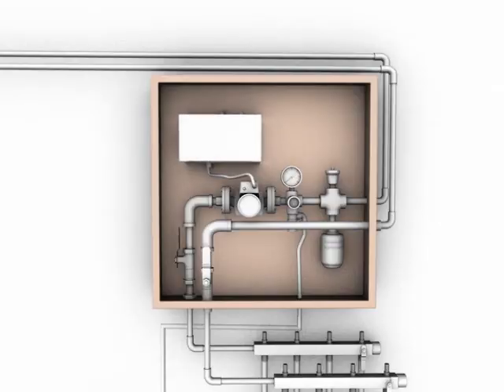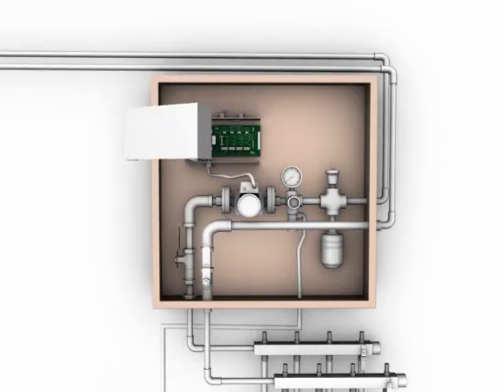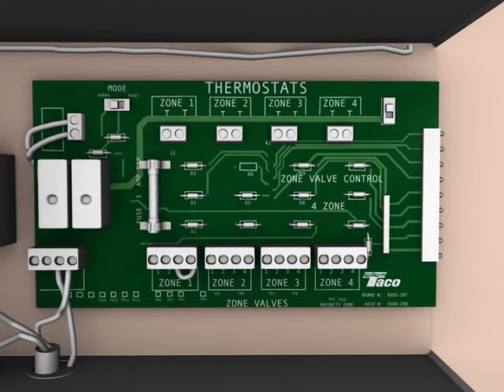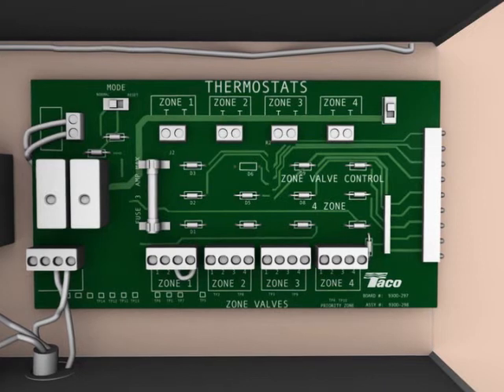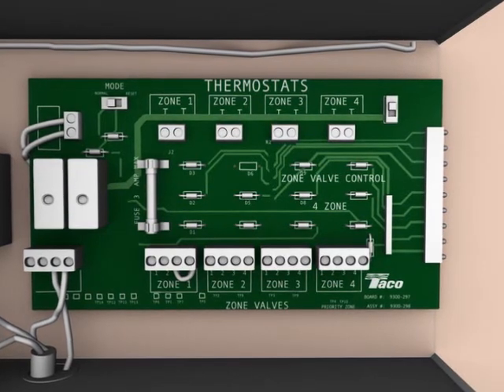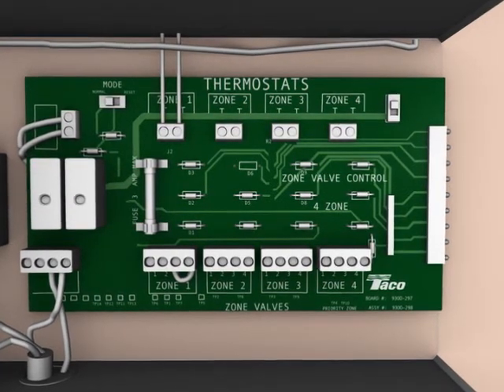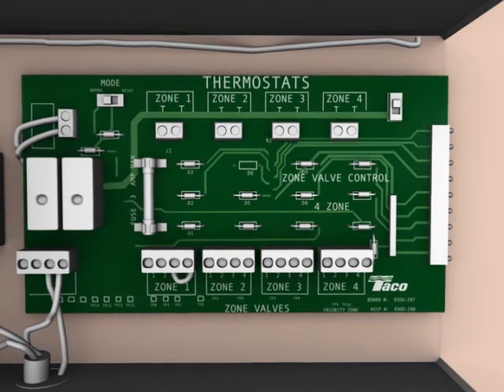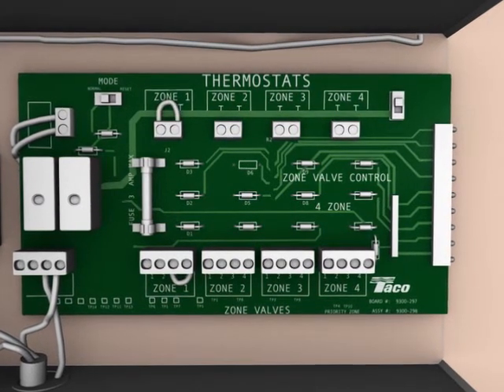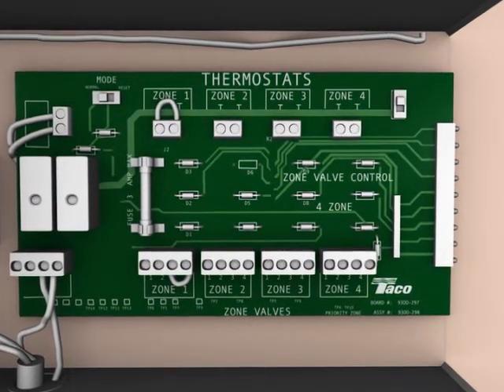Remove the cover from the TACO 4-zone controller within the control panel if the area with the radiant heating is to be controlled by a thermostat. Provide and install a low-voltage thermostat and connect it to the two Zone 1 thermostat terminals. If a thermostat isn't being used, provide a jumper wire between these terminals, allowing the pump to operate continuously.